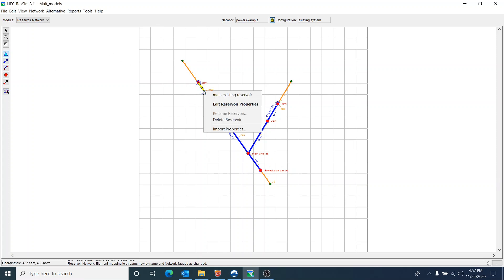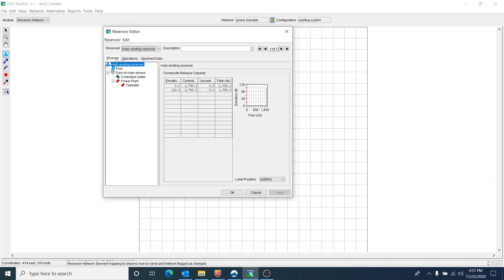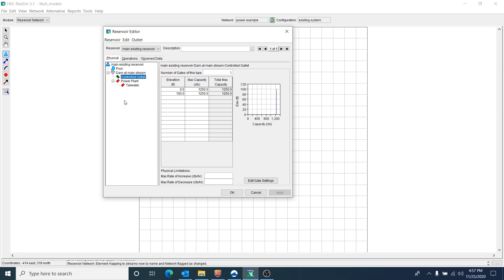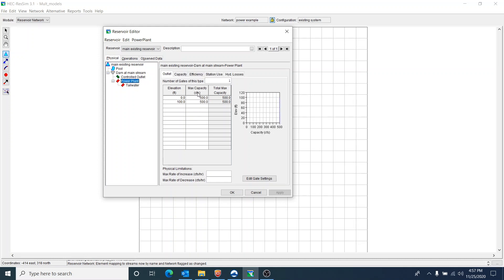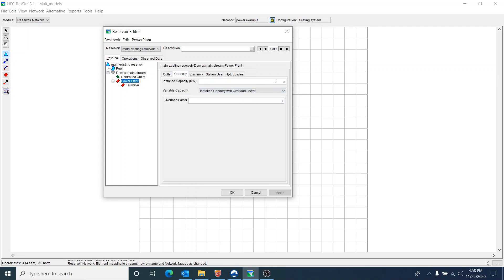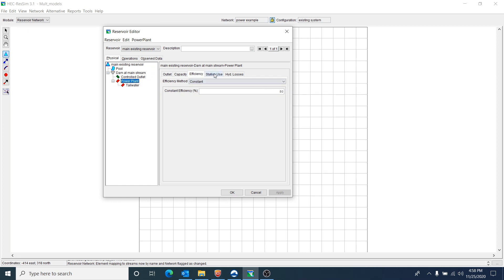If we go take a look at the reservoir, we'll first look at the physical properties. You can see I have a controlled outlet on this reservoir. It has a capacity of 1,250 cubic feet per second. I also have a power plant with all the parameters entered. It has a max capacity of 500 cubic feet per second, which does not vary with elevation. I have a capacity of 2 megawatts, an efficiency of 80%, no station use, and the hydraulic losses are set to zero. I tried to keep this very simple so that you'd be able to more easily interpret the results.